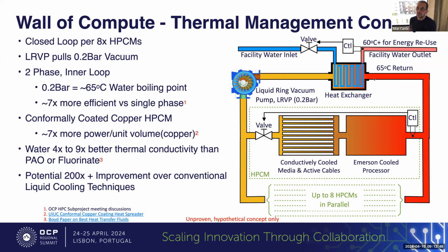And then the water comes up to the heat exchanger, and then we've got facility water, which again we need to control the flow of through the heat exchanger. So there'll be a certain drop, and I've just done 60 C here, which is then used for energy reuse. These are just examples - we've got another similar control loop going on the facility water for energy reuse purposes.